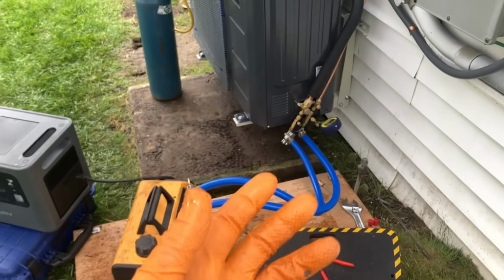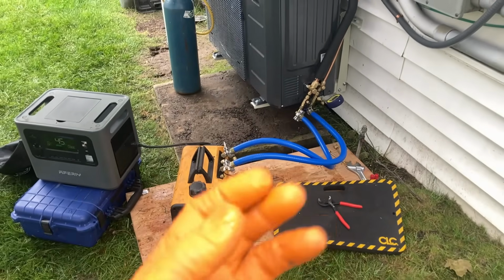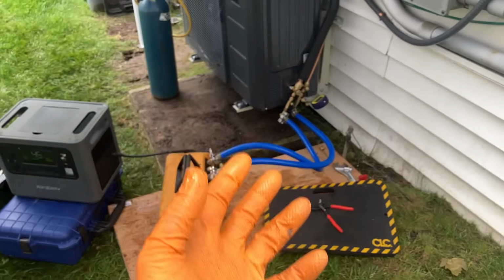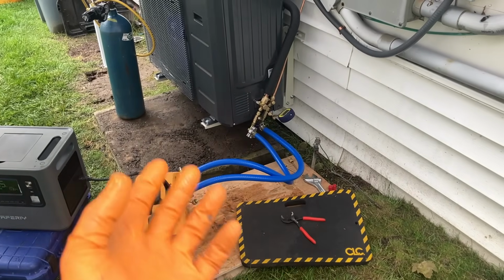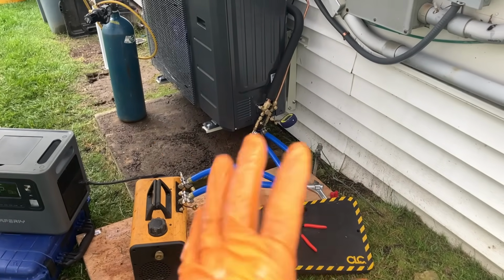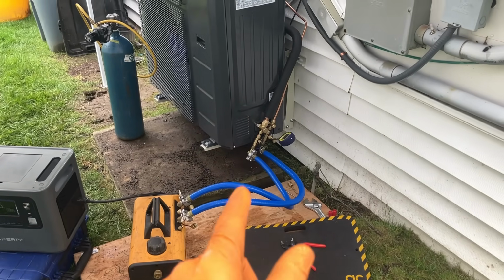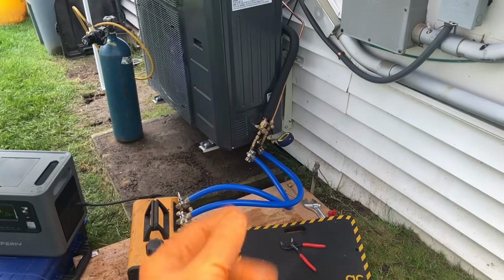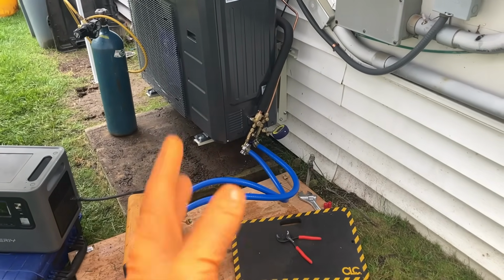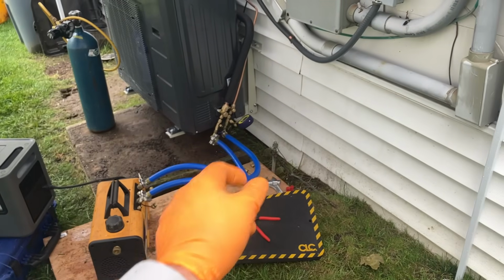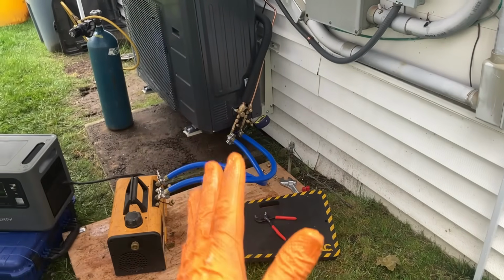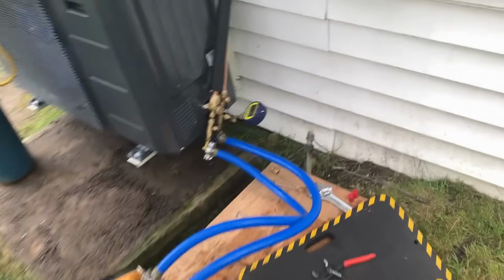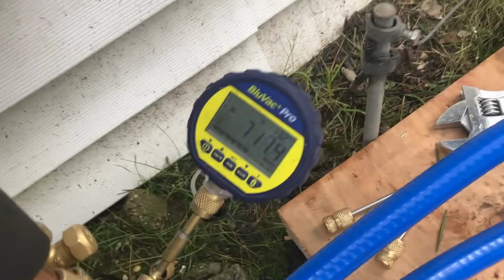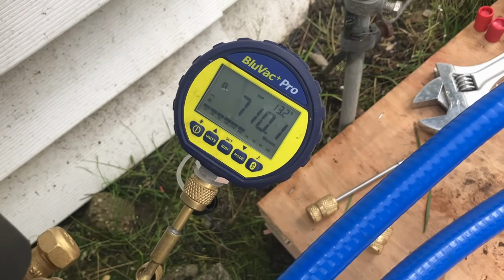Now when we're vacuuming down, we want to have a nice deep system that's free of non-condensables and dry. Industry standard is 500 microns, but at Pipe Doctor we try to get into the 40s and 30s. Now granted, it's not going to stay that way because as soon as I close those valves we're going to shoot up. But utilizing the ACiQ tools, the BluVac+ Pro micron gauge, look at that, 700 microns.